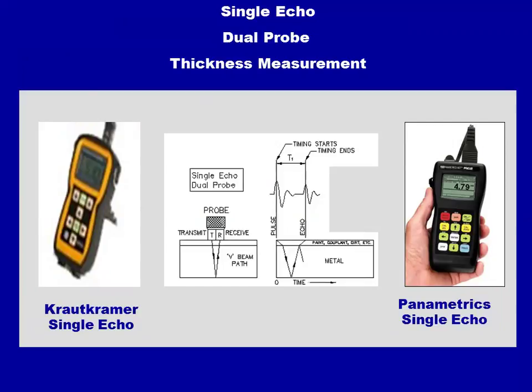It's given in physics that sound passes through certain materials at certain speeds. You calibrate the instrument to the velocity of sound of the material you're testing. Carbon steel has one number, stainless steel another, brass its own number, aluminum its own number. Each time you test a different material, you have to recalibrate the instrument to that material's velocity of sound.